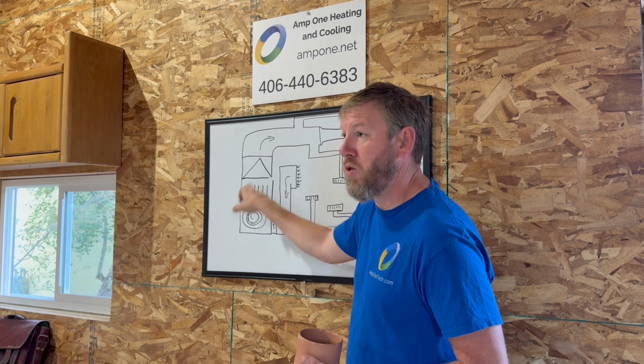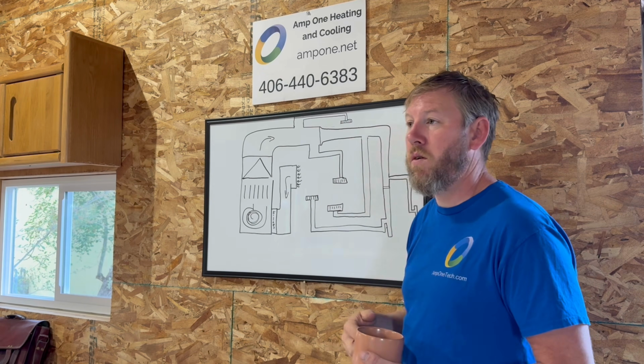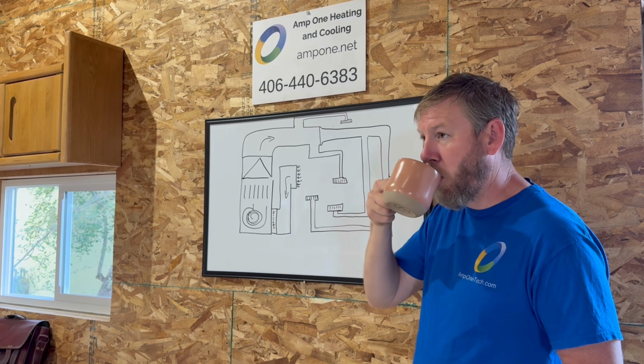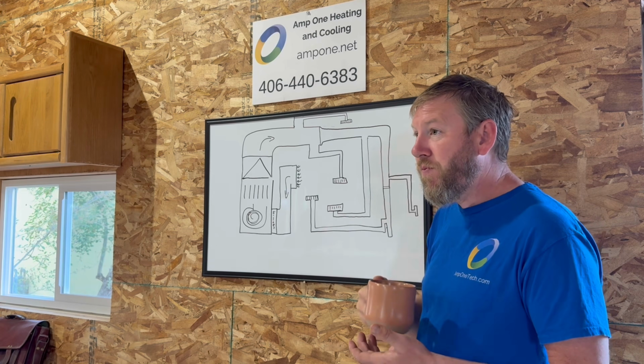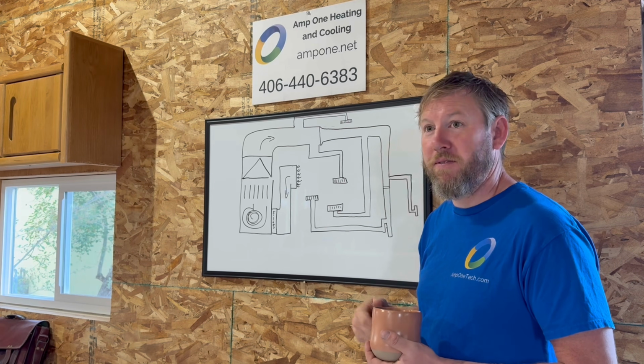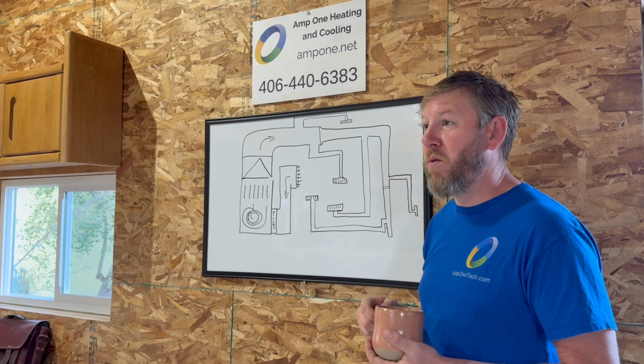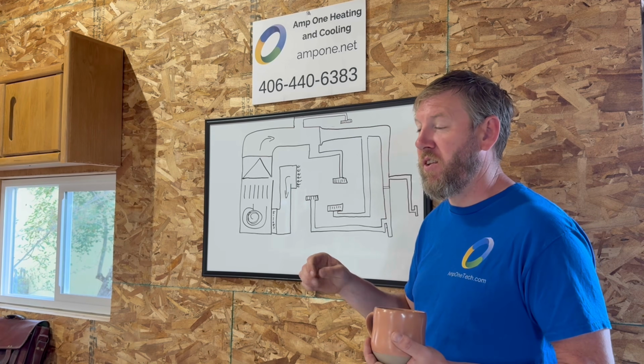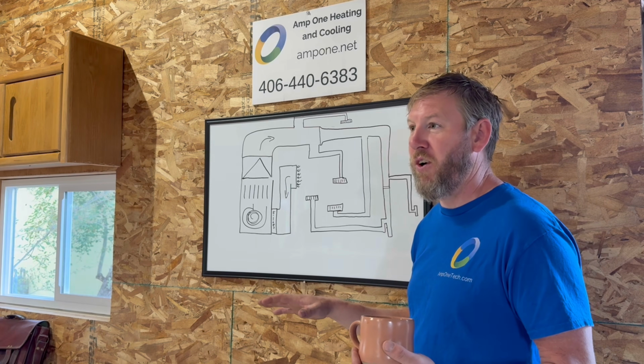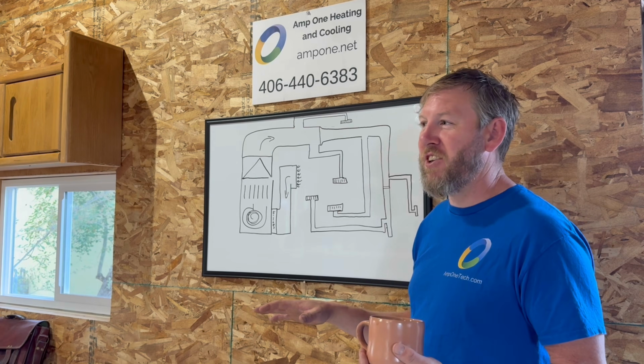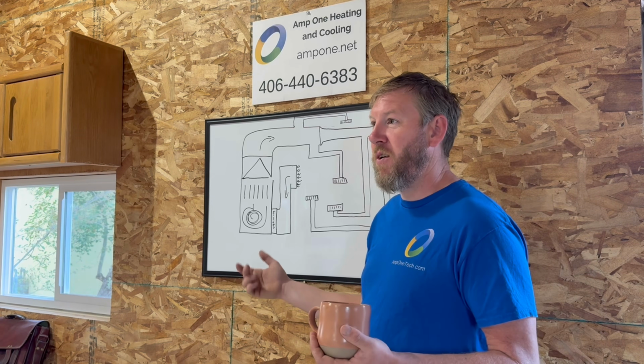What we're checking is just what's going on with the furnace. If we assemble all this and find out that there's not enough pressure, or too much pressure coming in, do we have to change the ducts? We have to make another... That's why we do math and we check everything, because we don't want to change it once it's already up in the attic and the insulation's blown in. So that's why I'm like, once you have enough of them, then it doesn't matter.